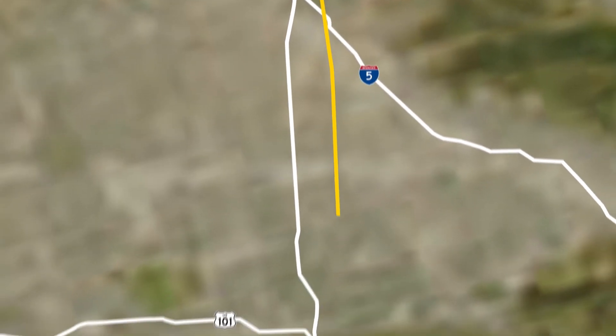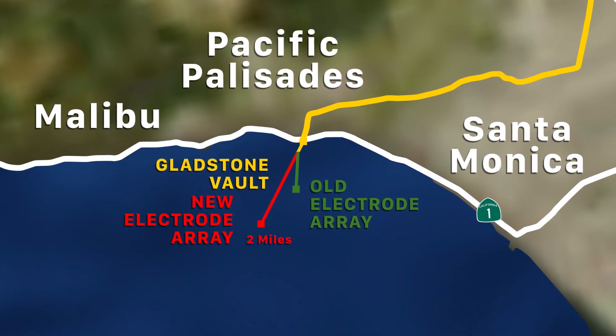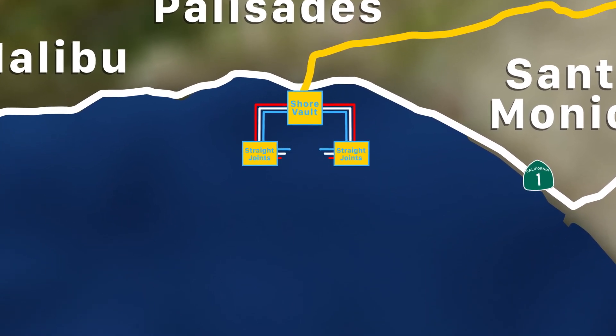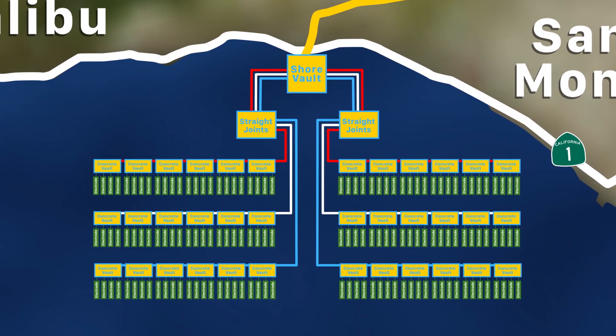The SGRS is comprised of two primary cables that are tied into the PDCI at our Sylmar Converting Station Facility. These cables run from Sylmar about 28 miles on overhead lines and 9 miles underground to Pacific Palisades. The system then extends two miles offshore out into Santa Monica Bay. At that point, the primary power cables tie into a large area electrode array that consists of 144 electrodes distributed throughout 36 large concrete vaults. The design of the array distributes the electrical discharge over a large area, which renders the discharging electrical current totally benign and safe for marine life, divers, and nearby infrastructures.